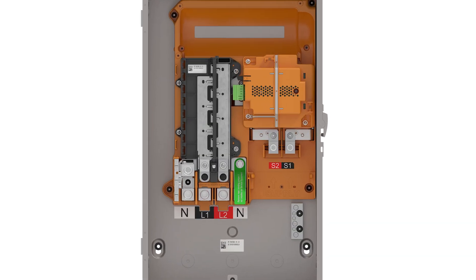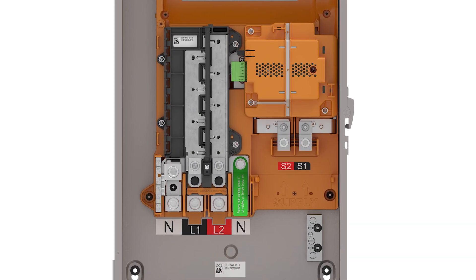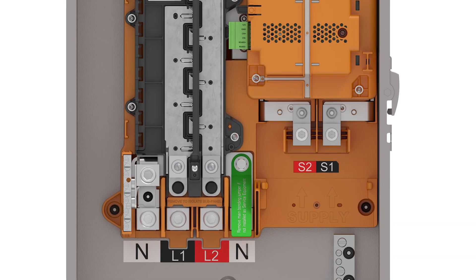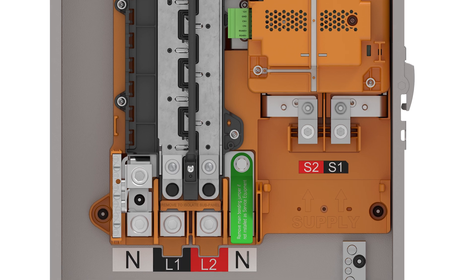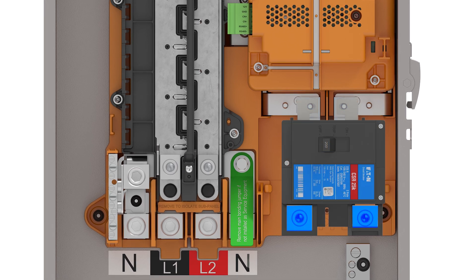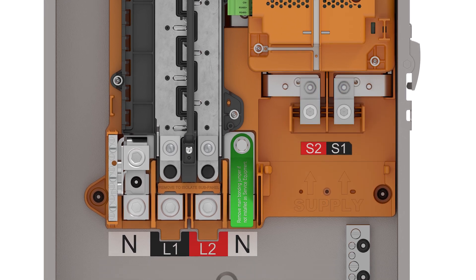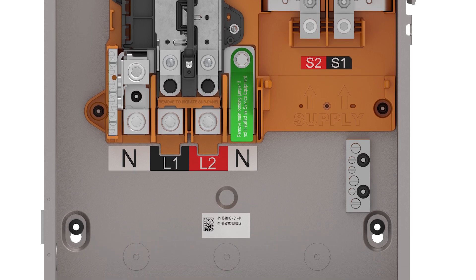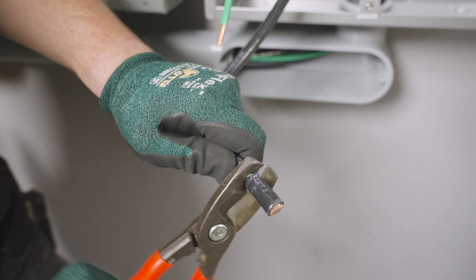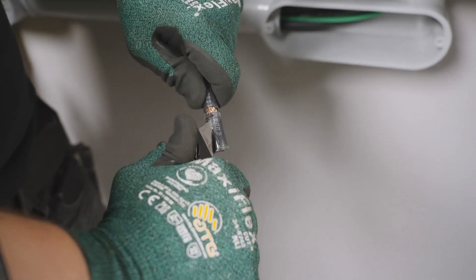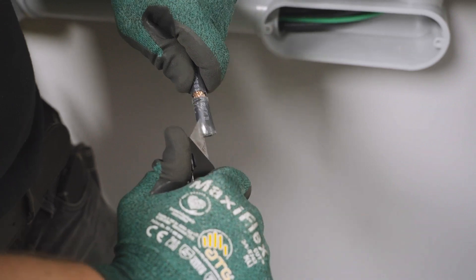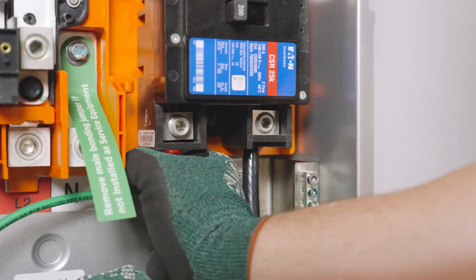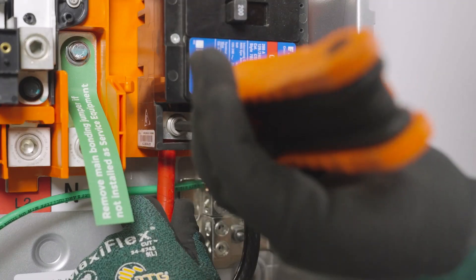With gateway prepped, begin wiring by routing the incoming line 1 and line 2 conductors to the supply terminals or main breaker. Route the incoming neutral and grounding conductors to their respective lugs. Strip the end of each conductor to the length specified on the equipment and terminate to the listed torque values.